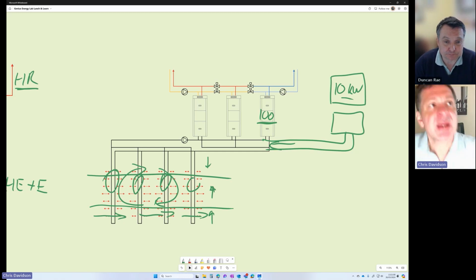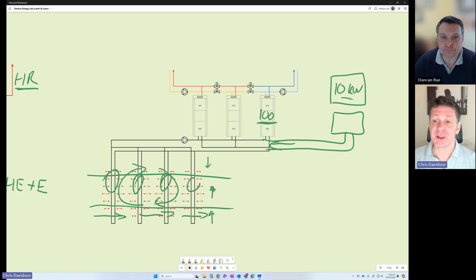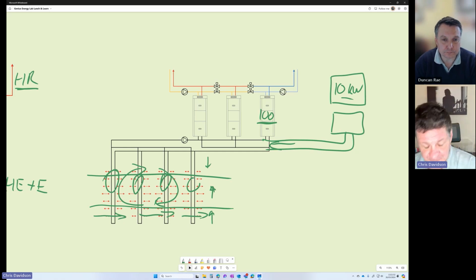Okay, thanks, Yash. Great question. So we've got a huge wealth of knowledge to fall back on. And in most cases, actually, we will be installing or designing systems that will be installed without on-site physical testing. And that's just because it wouldn't be affordable to do that testing. So we've got to risk assess what our knowledge base is like, and what that then says about the geology and the risk associated with a high or a low conductivity that we're actually going to get on the system. So what we'll be doing, if we've only got desktop information to go on, is asking: do we have local tests available to us? And we've got well over 300 local tests available to us that we can use in our analysis. And also, what's the variability likely to be in that specific ground condition that we are looking at? Some ground conditions are very, very precise, or we can be very precise in our desktop assessment of conductivity.